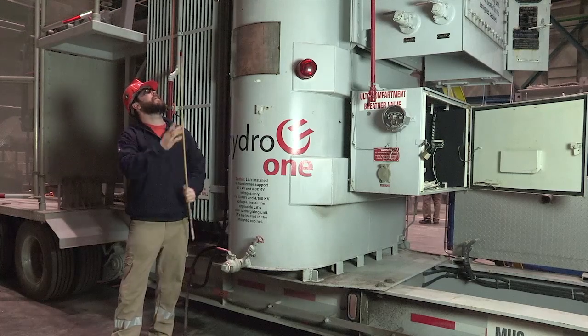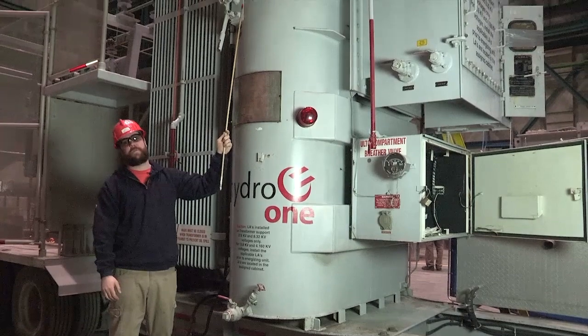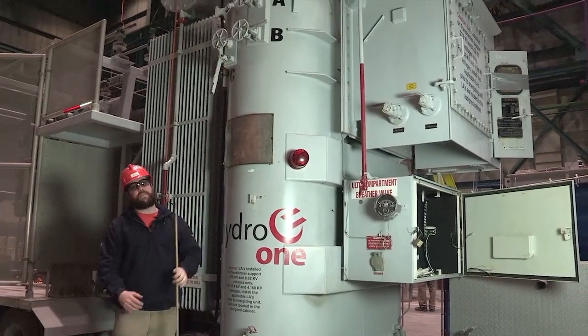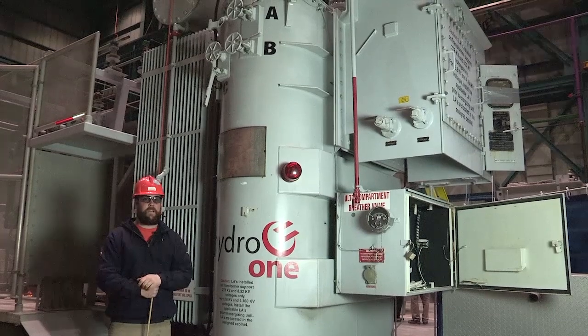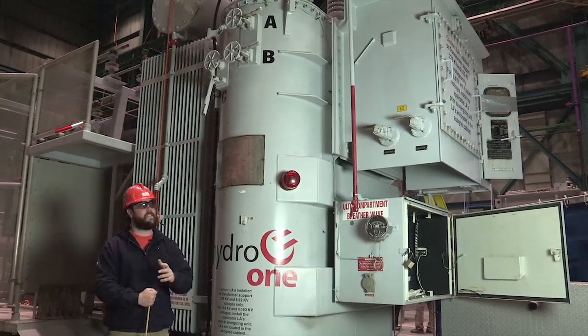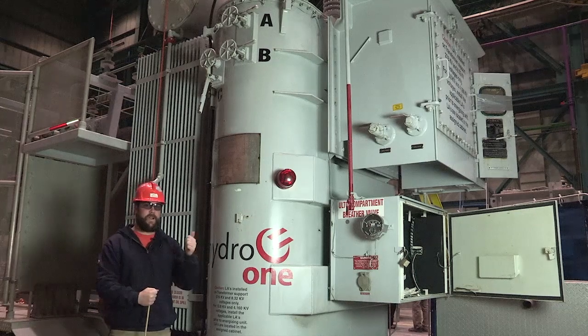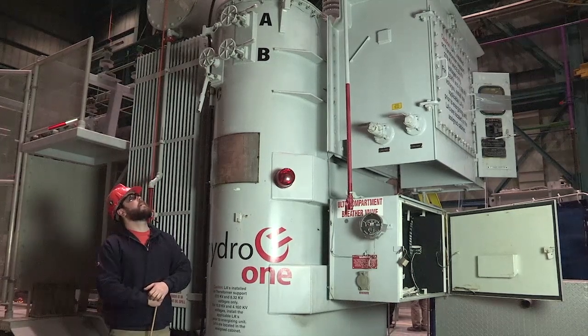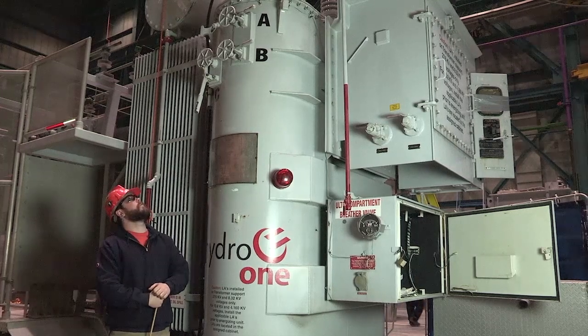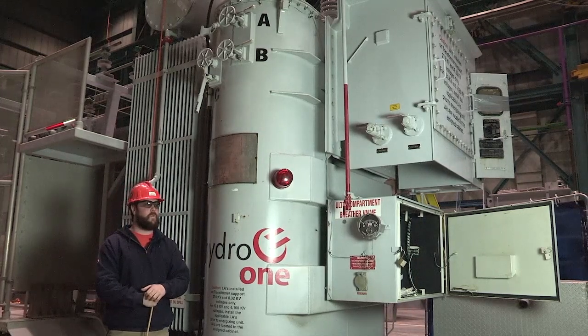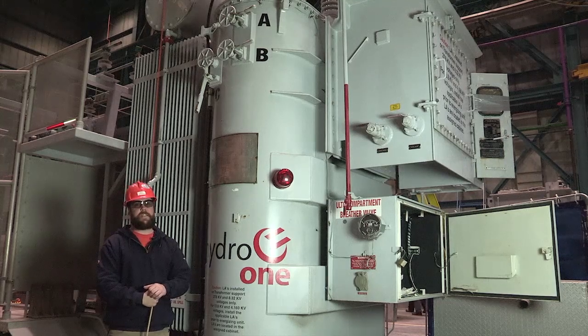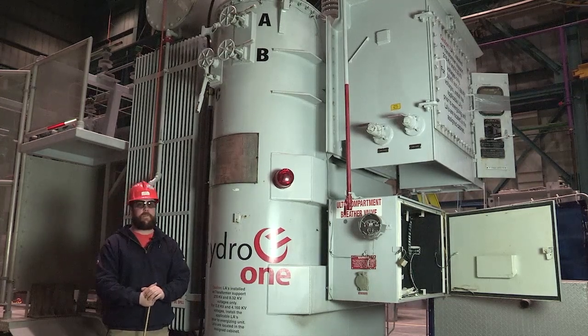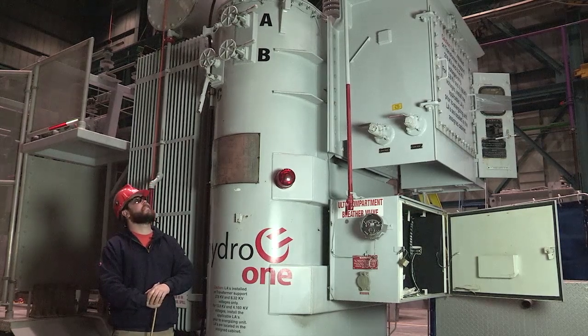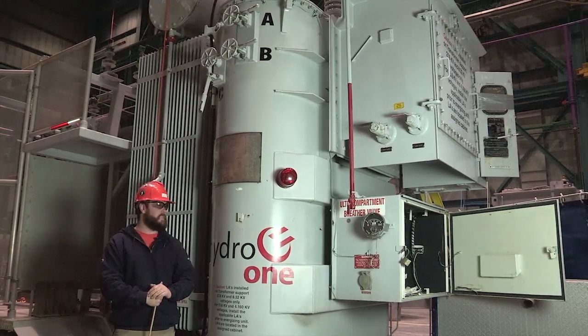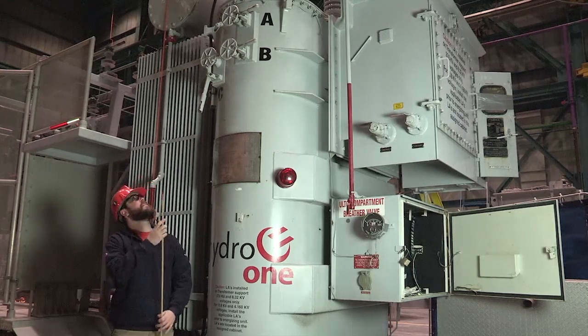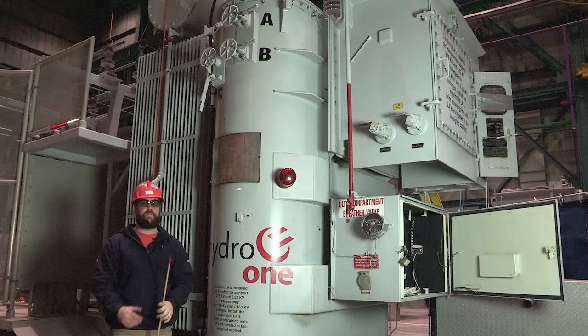And up here we have our OCTC parallel and series switches. You want to operate those. We've been having a lot of problems in the field with these seizing up after not being used for a while. You get salt and water and sand all in there. They're very difficult. That's the whole reason why this one is in CMS, because we had a broken shaft. So we're going to start operating them in the field a little bit more, get some play in them, because every time we bring them in and we're able to move them, we end up cleaning them up, greasing them, and within a couple months they're all seized up again. So it's good that every time you're throwing one of these MUSs in, you inspect the handles and make sure the shafts are moving freely.